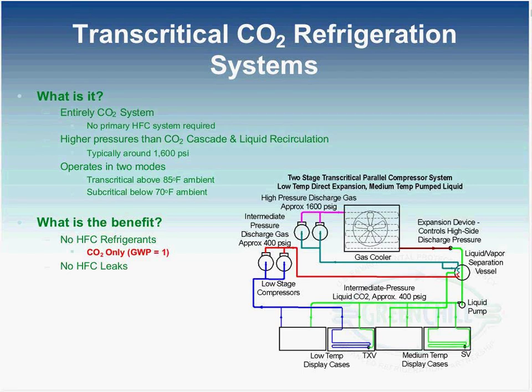But what I've heard from Bruce and Scott and Dustin and Sue around the CO2 secondaries and ammonia systems, we've all heard where there's a primary system which removes the heat from the secondary system, be it glycol or CO2. So an HFC refrigerant or ammonia is used to remove the heat from the refrigerant or liquid that's circulating through the display cases and walk-in units to maintain the temperature of the foods. With transcritical CO2, high side equipment is no longer necessary. It's not used. CO2 is the only refrigerant being used at all. It's compressed and it's also circulated through the store. So there's no other refrigerant except carbon dioxide.